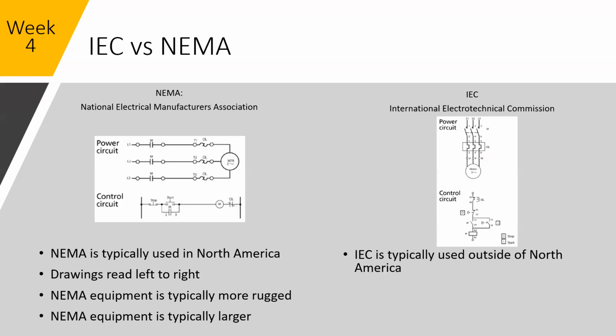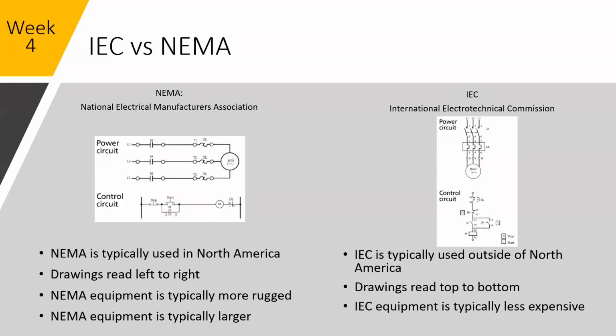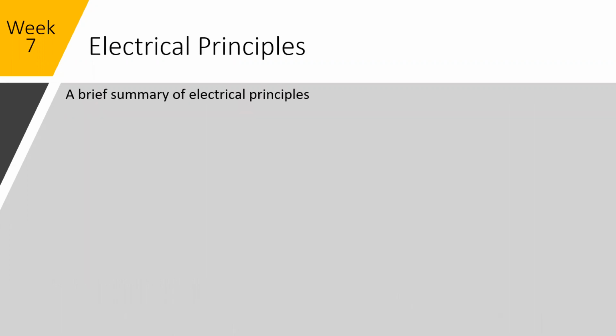IEC, typically used outside of North America, like I was saying. Drawings are read top to bottom. IEC equipment is typically less expensive because when you size things up, especially for electrical, you're adding more copper, you're adding more metals, precious metals to them. So they cost more. And typically this equipment is more compact. So one of the things that you have to contend with when you're looking at IEC rated equipment versus NEMA rated equipment is some of them wouldn't pass spec in different countries, if that makes sense. You can get some things that'll be fine for the EU and follow IEC standard, but if it doesn't meet CSA, it can't go in Canada. That's something that we can cover later.